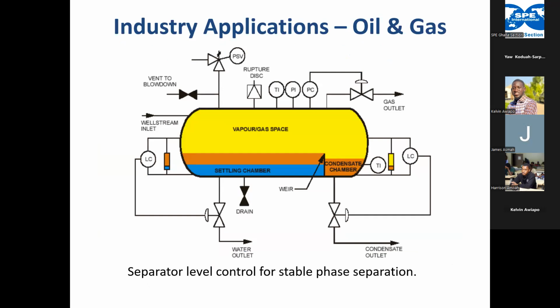You look at some applications in the oil and gas. One of them is separator control, which means a separator that is applying level control to avoid maybe spillover or something. So this is a three-phase separator. We have water, which is the heaviest, at the bottom. And then we have the condensate on top, and then we have the gas.